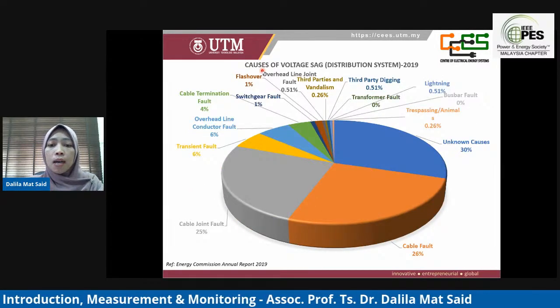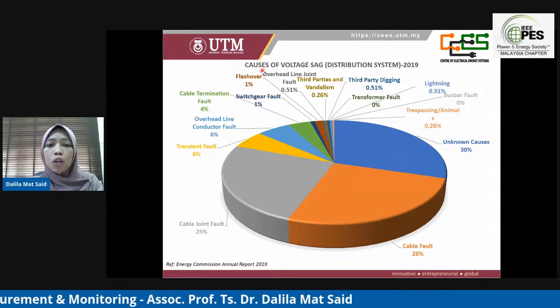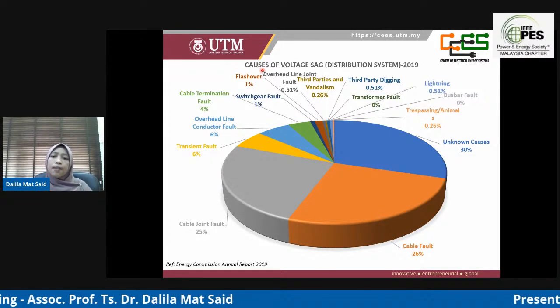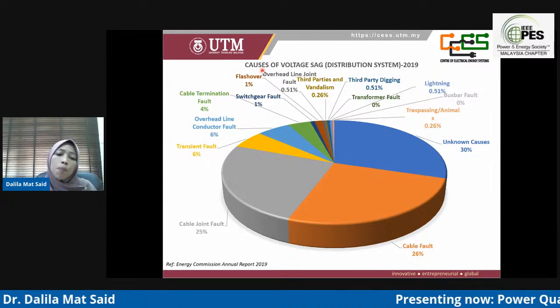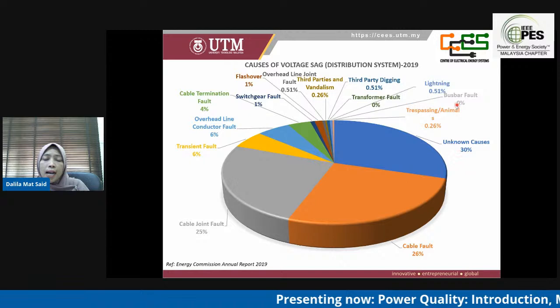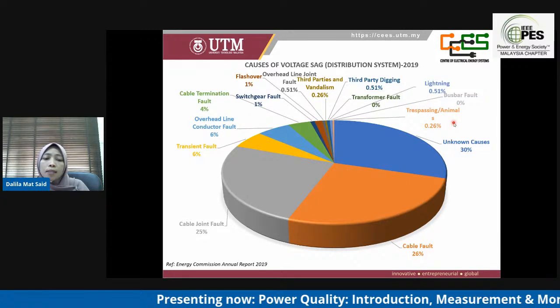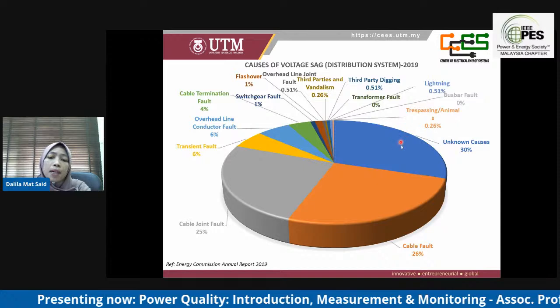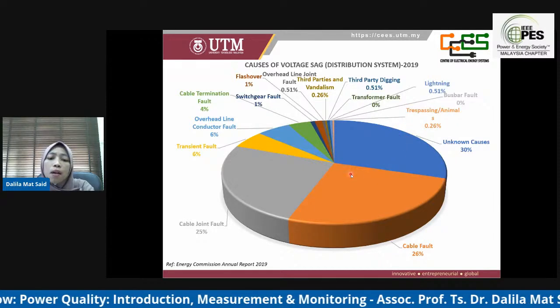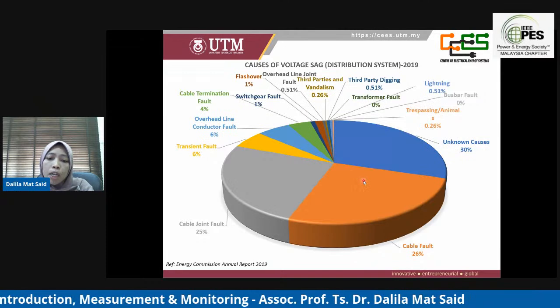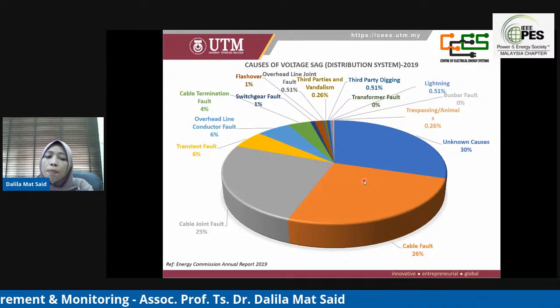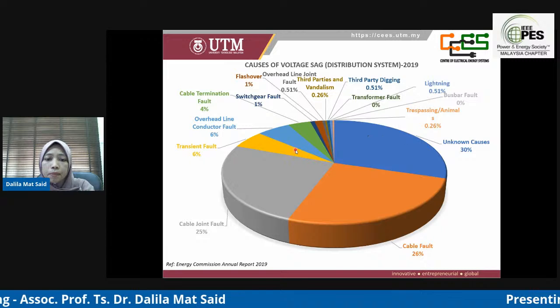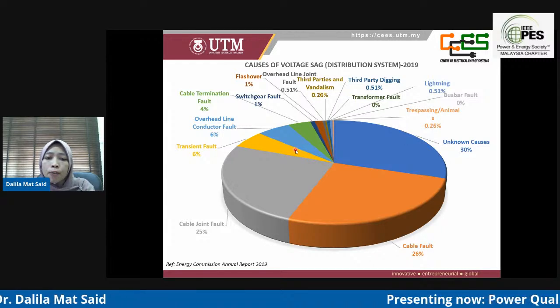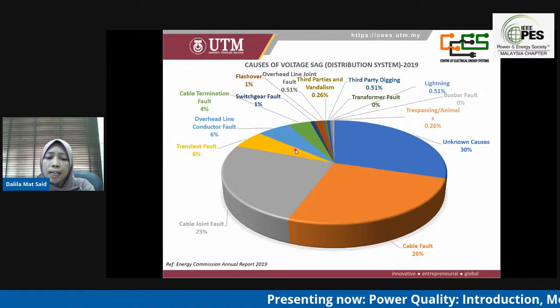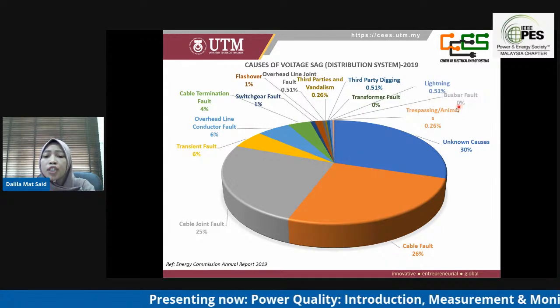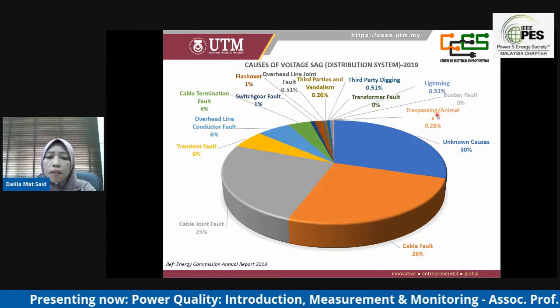However, at the distribution line or distribution system, we can see most voltage sags were due to unknown causes. Other causes include damaged cable, cable fault, damage on cable and cable joint, transient fault, and damage to the overhead line conductor. And usually the highest cause, unknown, refers to a transient or internal fault at the customer side.